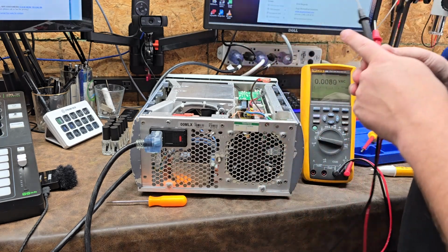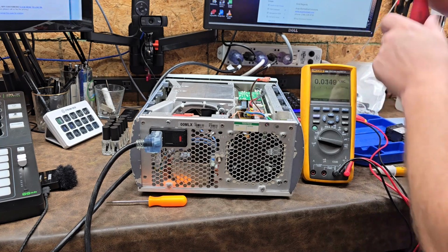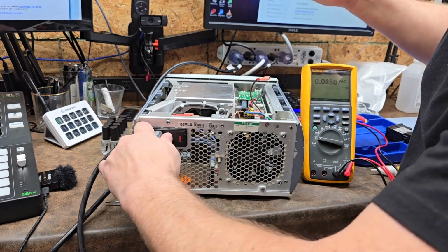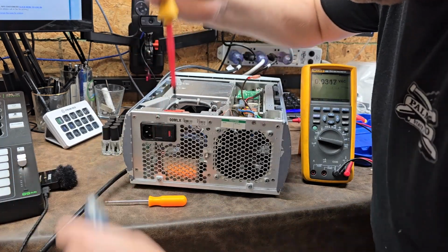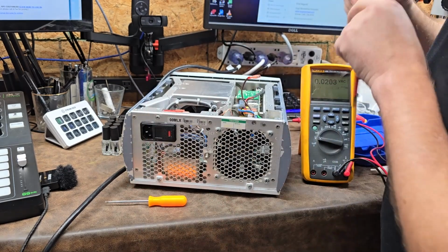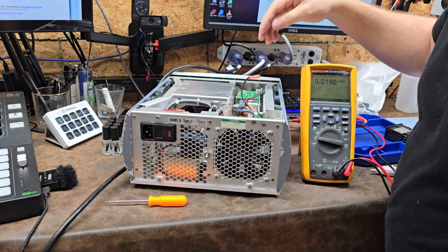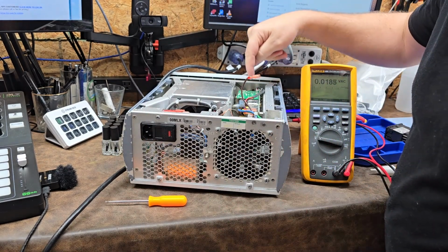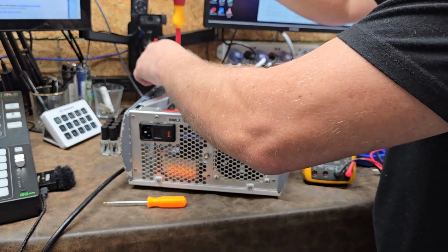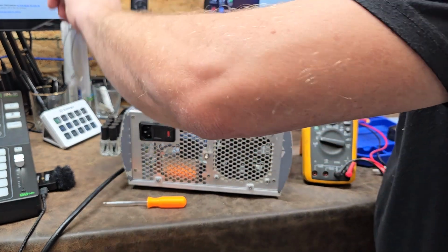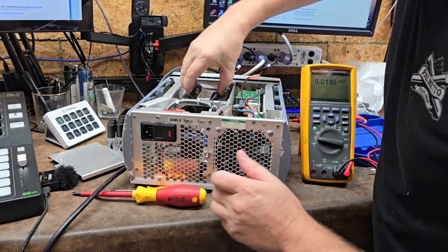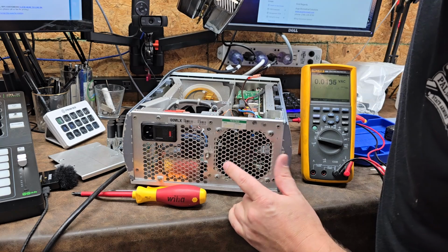Okay folks, let's go ahead and take that out. Let's check the bulb, disconnect power. We just had this guy energized earlier when it popped the fuse, so there could still be voltage on that high voltage tank, so let's be very careful of that. Let's inspect that bulb and see if we have any signs of issues.